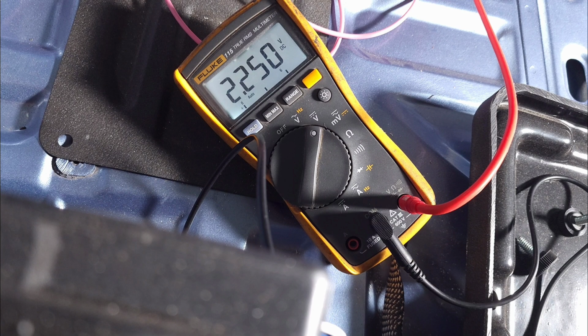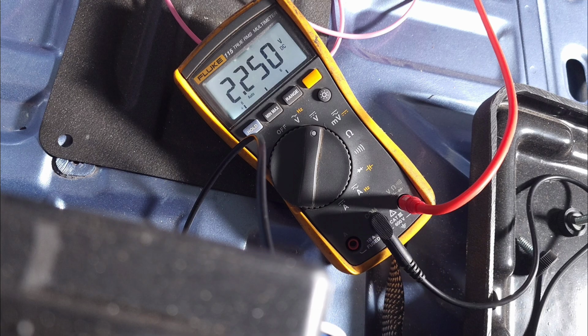Through the magic of editing, we can pause it and see 2.25 as it flashes on the screen. This is, of course, an absolutely terrible amount of voltage to lose on a piece of 12 gauge powering a couple lights. And if you pay close attention, you probably noticed that it went higher than that, to 3 point something volts.